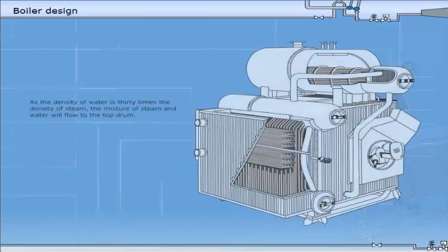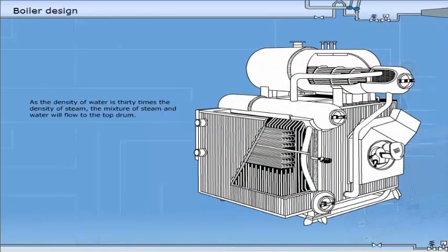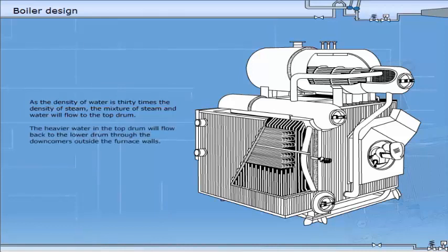As the density of water is 30 times the density of steam, the mixture of steam and water will flow to the top drum. The heavier water in the top drum will flow back to the lower drum through the downcomers outside the furnace walls. The steam-water mixture travels around in the boiler at a velocity of 0.3 to 1 meters per second.